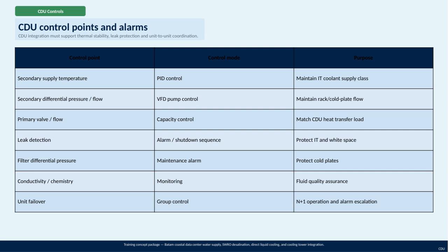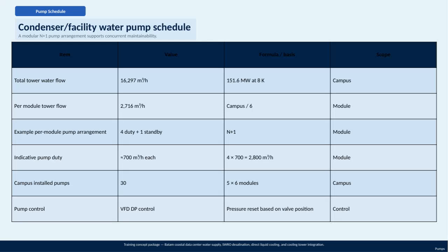On top of these control points, the training concept package covers an integrated approach involving Batam Coastal Data Center water supply, SWRO desalination, direct liquid cooling, and cooling tower integration, demonstrating a comprehensive strategy for effective CDU management. Here we have the pump schedule for the condenser and facility water systems at our Batam Coastal Data Center. The pump configuration follows a modular N+1 arrangement, which means for every module, there are 4 pumps running and 1 standby pump ready to take over if needed. This setup ensures that maintenance can happen without interrupting cooling operations, supporting continuous reliability.